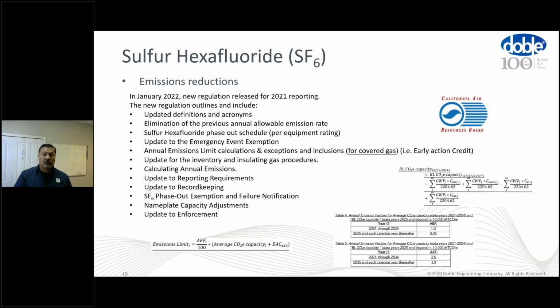There's an SF6 phase out schedule, and that's per the equipment rating. There's an update to the emergency event exemption, annual emissions limit calculation, exceptions and inclusions for covered gas. The reason this part changes is because they're not only considering SF6, they're considering SF6 gas alternatives. And it also allows for an early action credit for an SF6 user who implements alternatives into their system. There's an update for inventory and insulating gas procedures. Calculating the annual emissions has changed. Update to the reporting requirements, update to the record keeping, and of course, mentioning that there's a phase out of SF6. There's also an exemption and failure notification update on the new regulation.